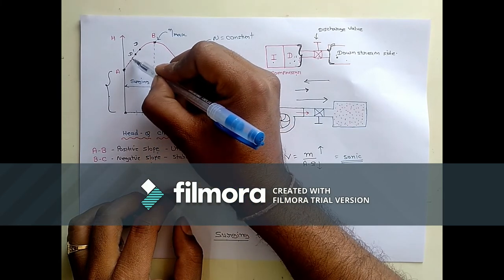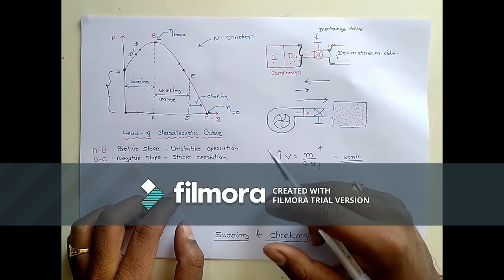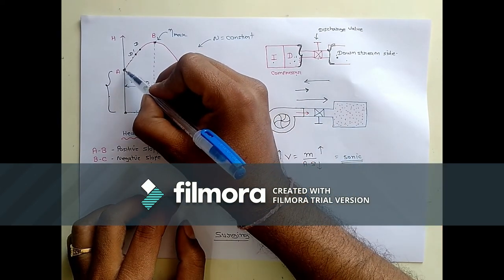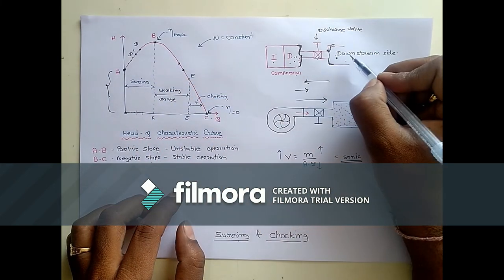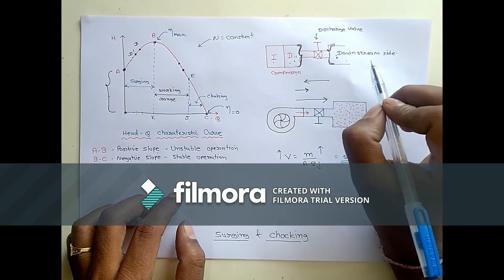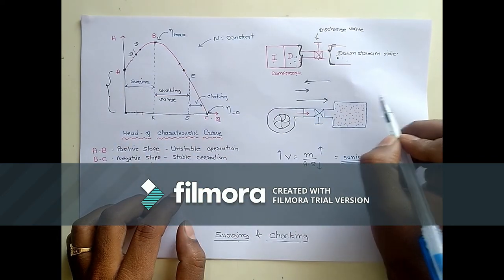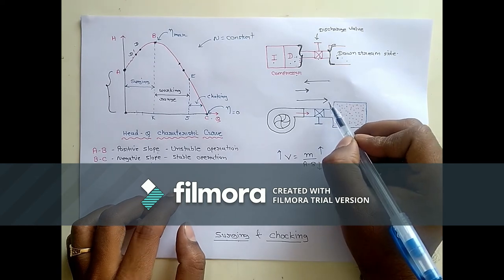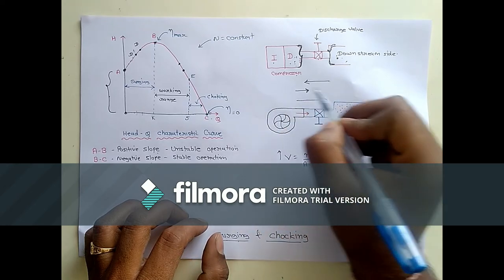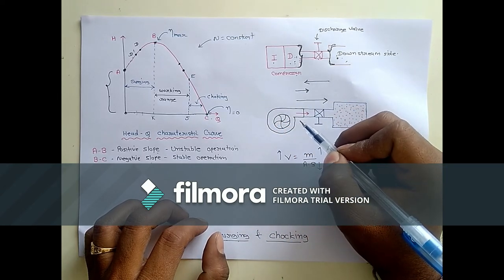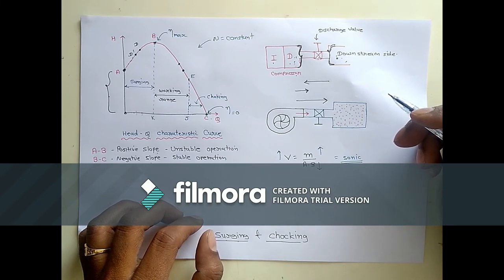Now the discharge is low and we are getting additional flow from the reverse direction, so discharge decreases further and pressure also decreases. It will decrease down to point A, beyond which the pressure will not decrease because the impeller imparts some energy. So reverse flow is possible only up to point A. As the downstream side pressure drops gradually, when the downstream pressure becomes lower than the pressure at A, the flow will again go in the forward direction because the compressor side pressure is now higher. This to-and-fro motion of the air is known as the surging process.